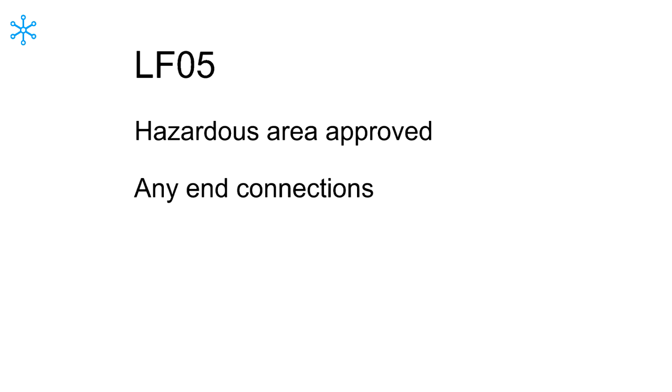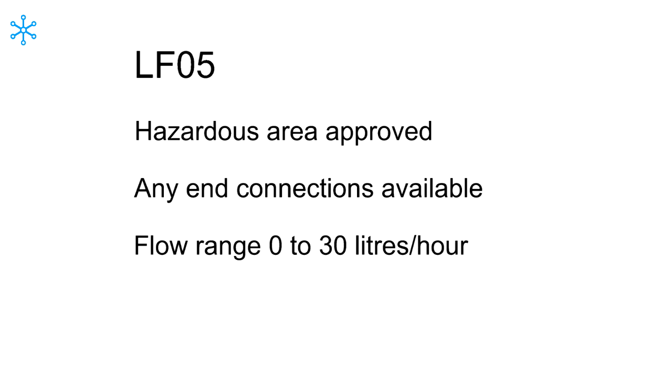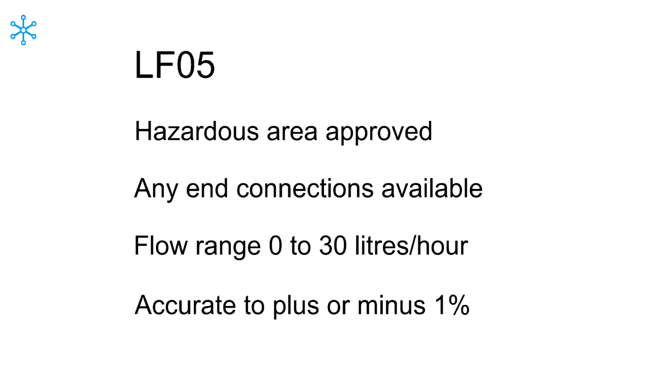Available with any end connections to meet the needs of individual applications, the LF05 has a flow range of 0 to 30 liters per hour and is accurate to plus or minus 1%, with plus or minus 0.5% linearity and plus or minus 0.25% repeatability.